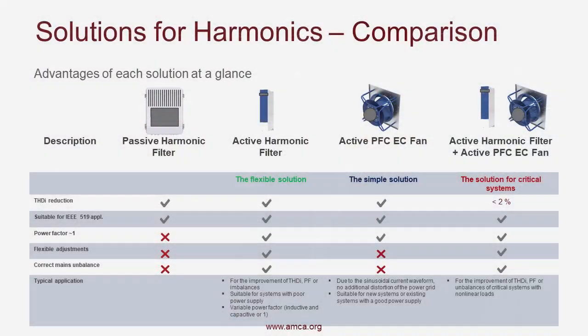So this might be a good solution for a system that doesn't have any power quality issues. There's no harmonics on the system or coming power quality issues. It's just you don't want to add anything to the system. And then maybe for a solution for a critical system would be using a combination, the active harmonic filter, external and internal.